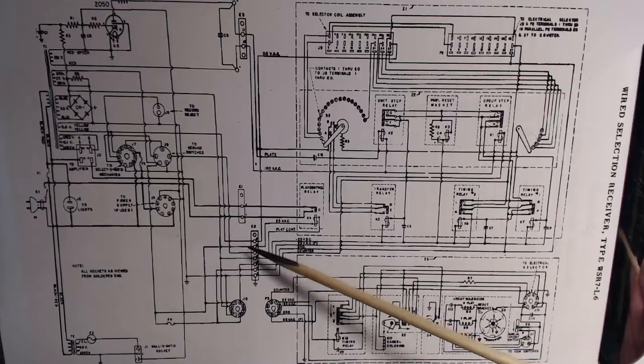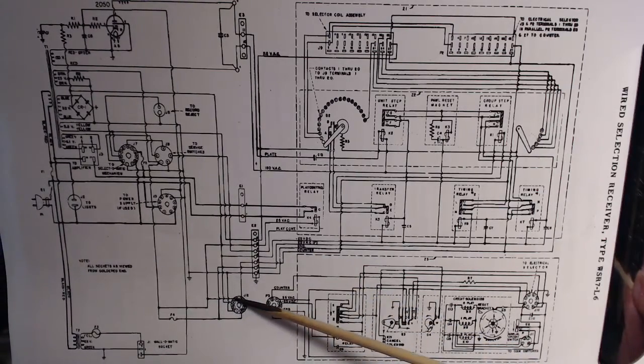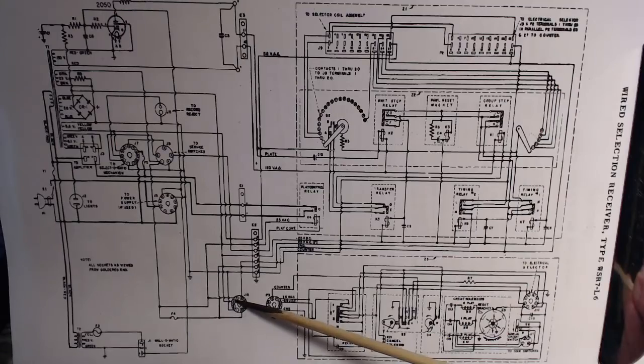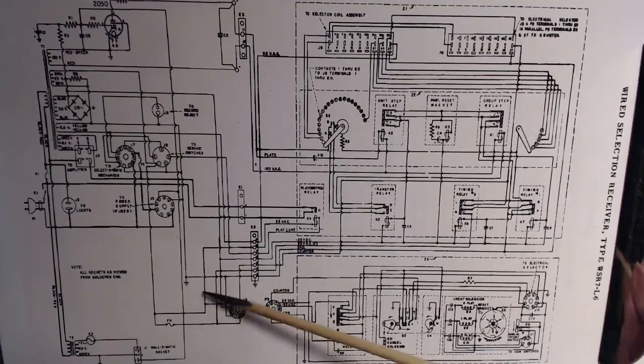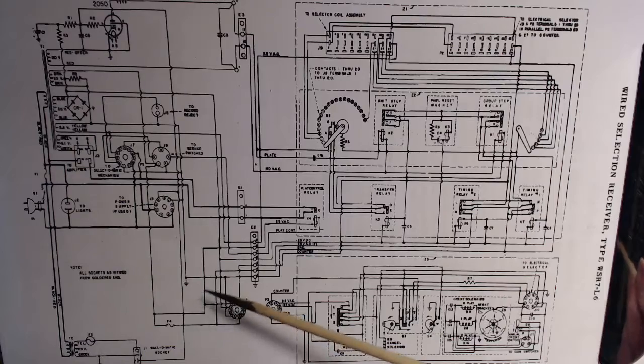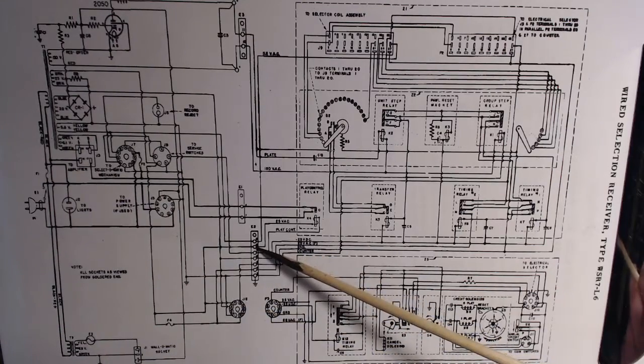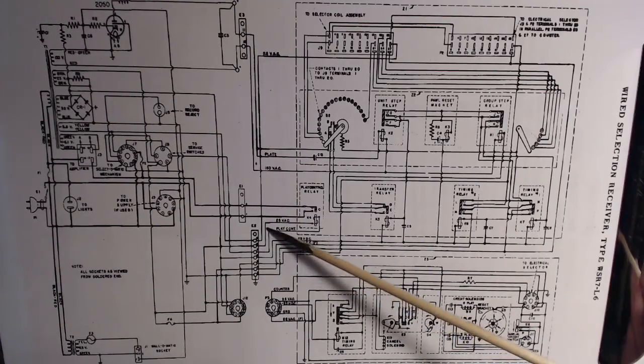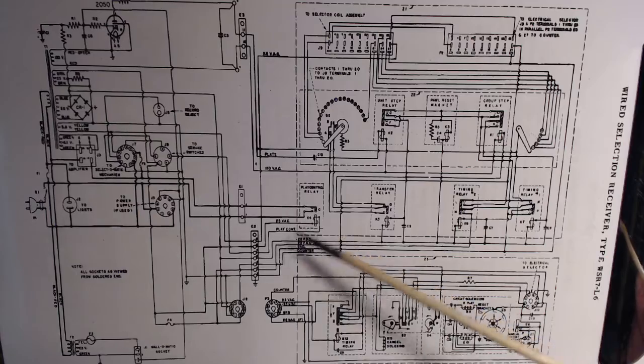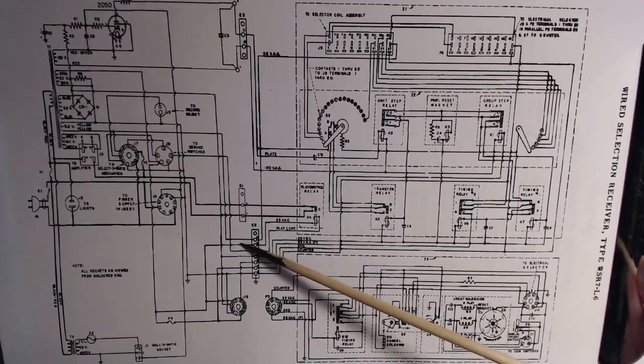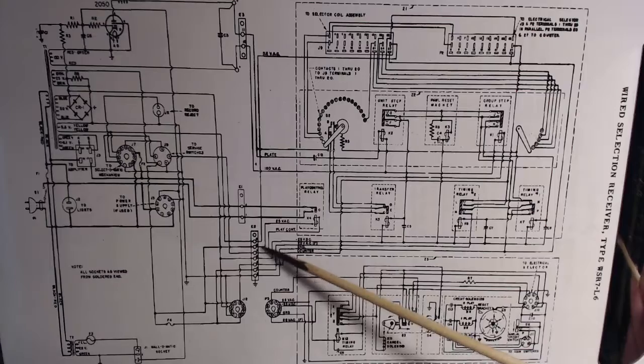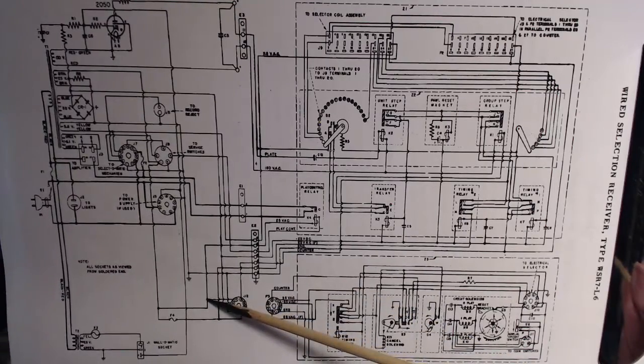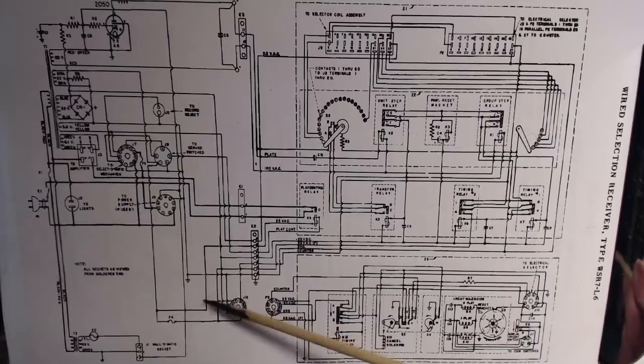Okay. Now the other wire that burned is this one. And you could stare at this schematic all day and really have a hard time explaining anything. Because this wire here that comes away from this terminal, this wire here, not burned. Burned. Not burned. Because this connection, of course, doesn't really exist. You don't make connections just out in the middle of wires.